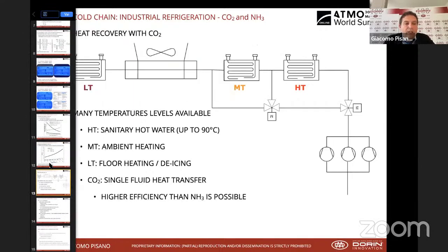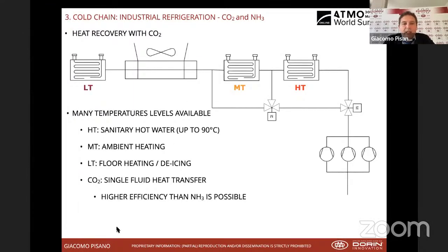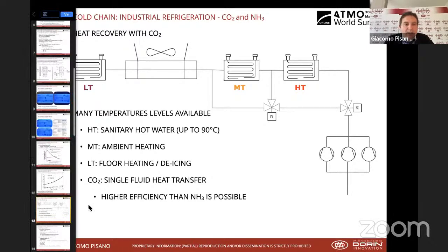When it comes to heat recovery, CO2 is able to provide so-called waterfall heat recovery possibilities. Basically, with CO2, you can have high temperature water available up to 90 degrees C, medium temperature water available up to 60 degrees C, and also low temperature available, like 20 degrees C, which can be used for floor heating of cold rooms or for de-icing cold rooms and all other areas where human beings have to access an extremely cold, closed environment, where the floor may be icing every now and then.